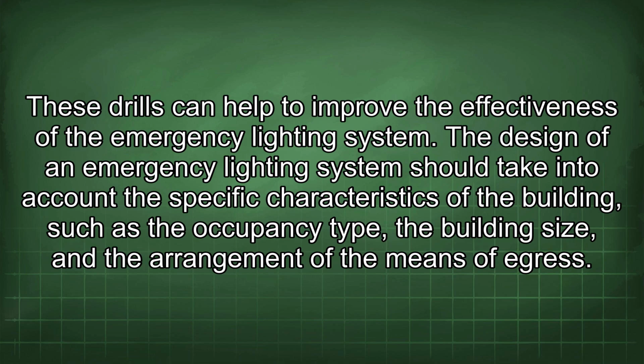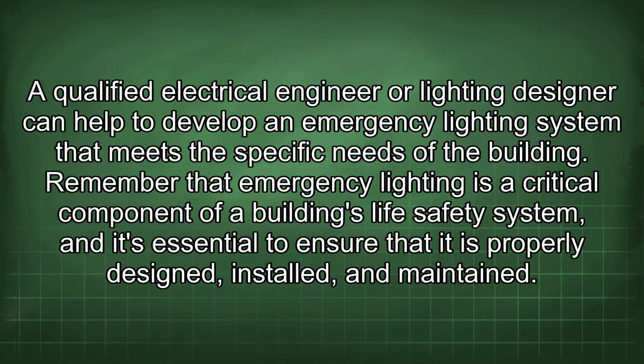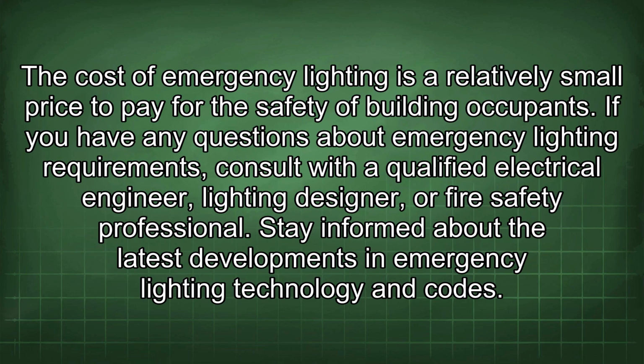The design of an emergency lighting system should take into account the specific characteristics of the building, such as the occupancy type, the building size, and the arrangement of the means of egress. A qualified electrical engineer or lighting designer can help to develop an emergency lighting system that meets the specific needs of the building. Remember that emergency lighting is a critical component of a building's life safety system, and it's essential to ensure that it is properly designed, installed, and maintained. The cost of emergency lighting is a relatively small price to pay for the safety of building occupants.